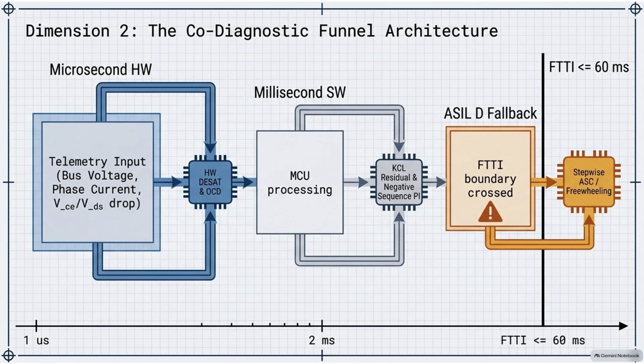And through capacitive coupling, that noise can actually leak into the diagnostic pathways. So it charges up the tiny filtering capacitor in the monitoring circuit? Yes. The system has a hard threshold, usually around 7 volts. If the voltage on that pin hits 7 volts, the hardware just assumes a catastrophic short is occurring. The high-frequency noise can easily pump enough parasitic charge into that capacitor to trip the 7-volt limit. Wow. So the chip panics, it triggers an immediate shutdown, and the driver loses all vehicle propulsion on the highway. For a fault that didn't even exist. Exactly.